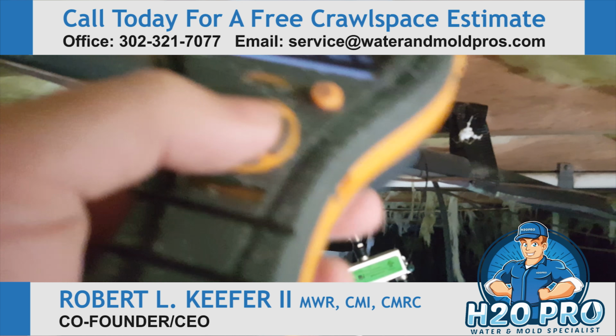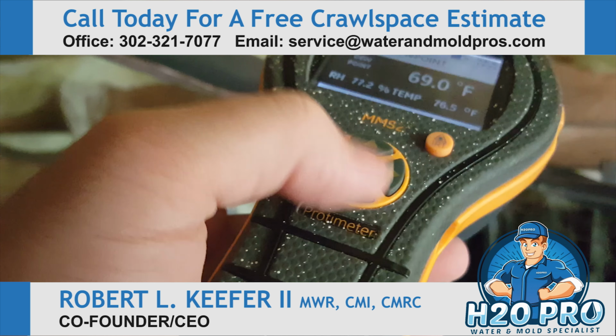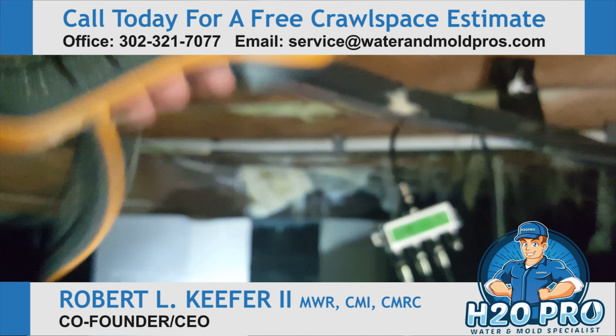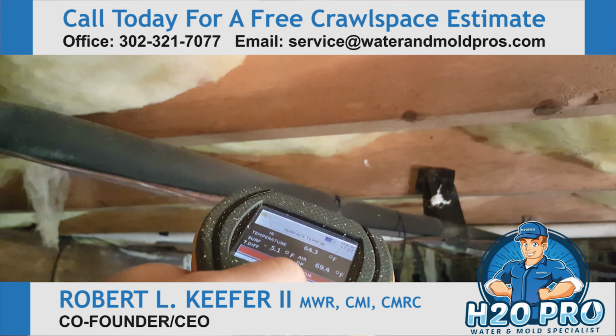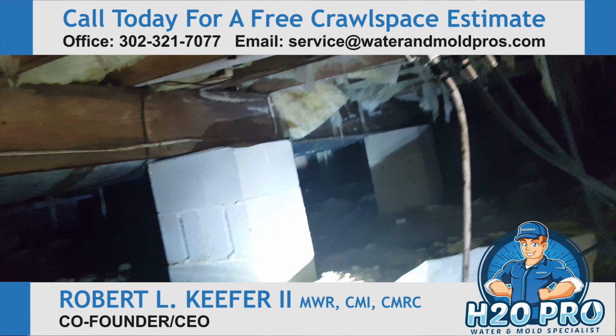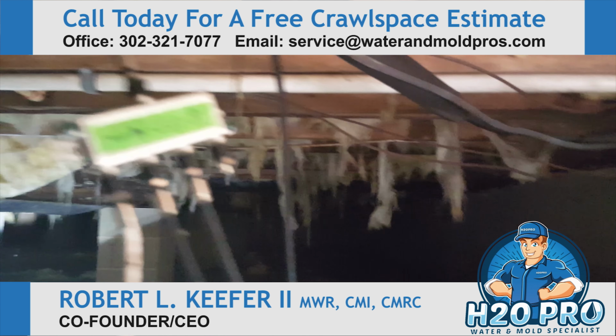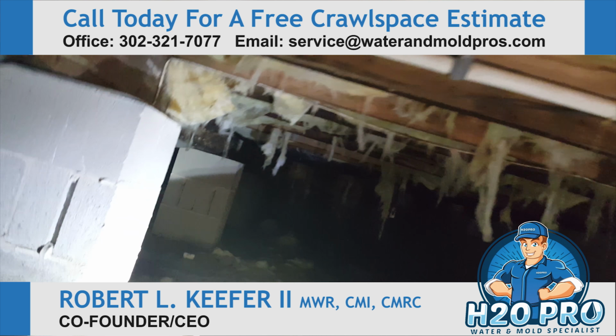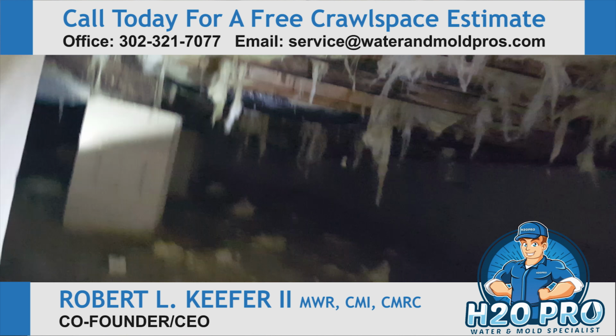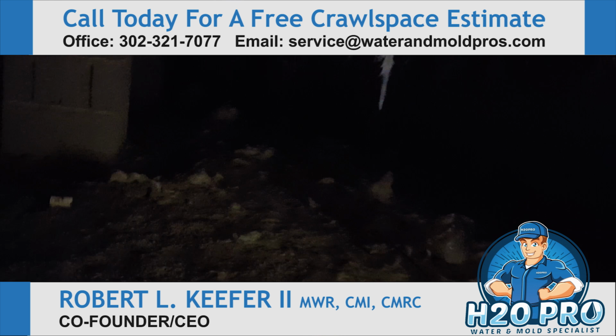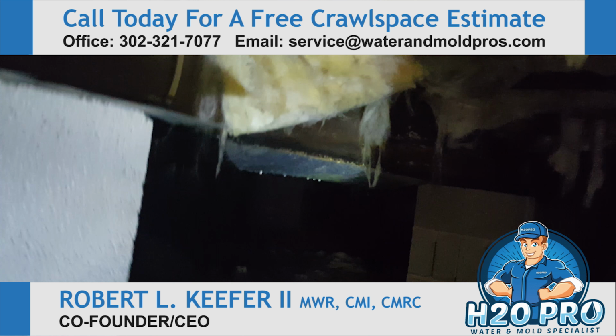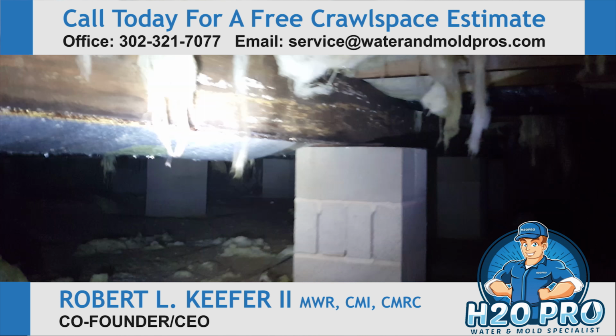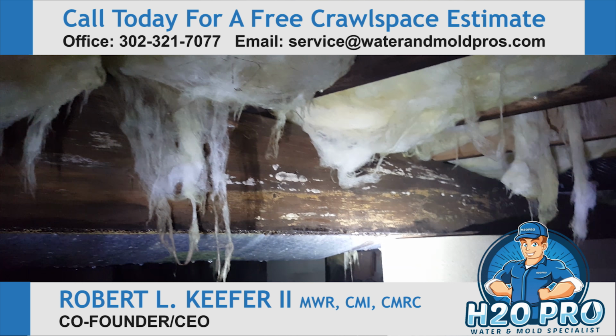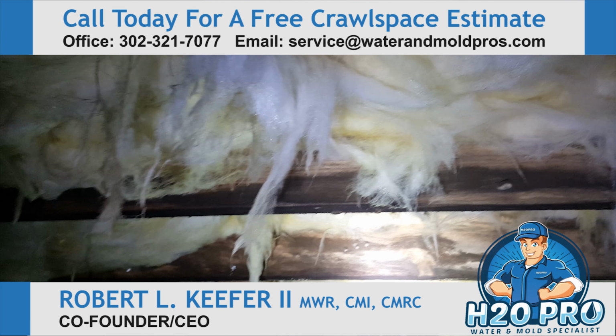Let's turn around and see if it's condensating up there. So the moisture's passed all the way up there. The insulation is wet, as you can see, starting to all fall down, lose its R value. And if you look further down here, there's no ground cover. Get my flashlight. And look at the mold growth that you see down on this floor joist. Look how black these floor joists are.